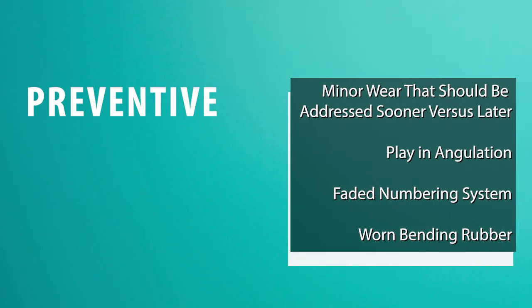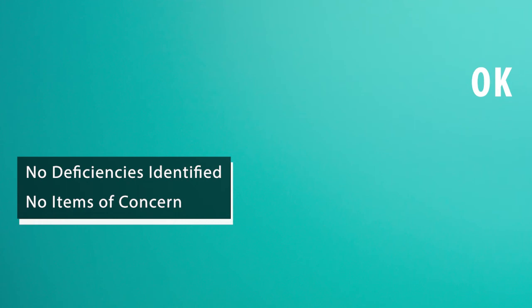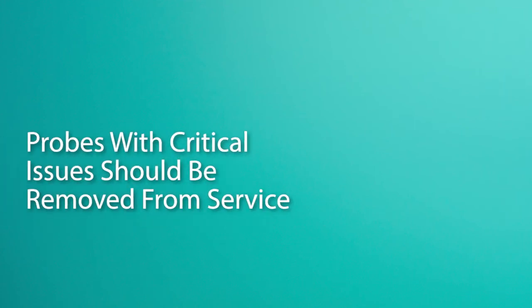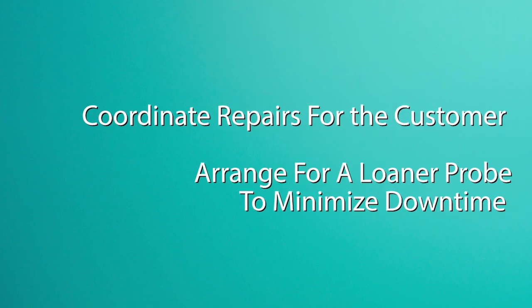Preventive can be used to classify probes that may not perform as well as intended. This may include probes with a worn numbering system, a worn bending rubber, or minor play in angulation. OK is used to classify a probe with no visual or mechanical issues. Any probes with findings deemed a patient safety issue should be addressed with an extremely high priority, and probes requiring service for minor cosmetic issues or minor issues with angulation can be considered a lower priority.